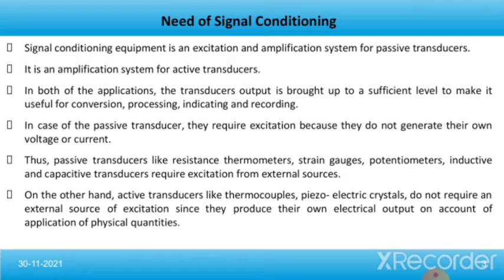In case of the passive transducer, they require excitation because they do not generate their own voltage or current. Thus, passive transducers like resistance thermometers, strain gauge potentiometers, inductive and capacitive transducers require excitation from external sources. On the other hand, active transducers like thermocouples and piezoelectric crystals do not require an external source of excitation since they produce their own electrical output on account of application of physical quantities.